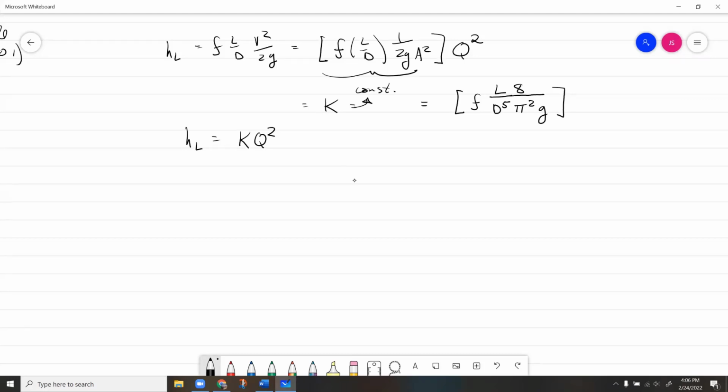All right, now we're going to define our loop, and we're going to say the sum of our head losses in the clockwise direction is equal to the sum of our K's in the clockwise direction times Q_C squared. You could imagine this is for each pipe, right? Each pipe has a flow. Maybe there are 2 pipes, pipe BC and CD or whatever that is, so you'd sum up the K Q squared for each of those pipes in that flow direction.